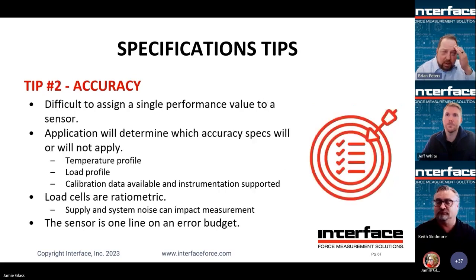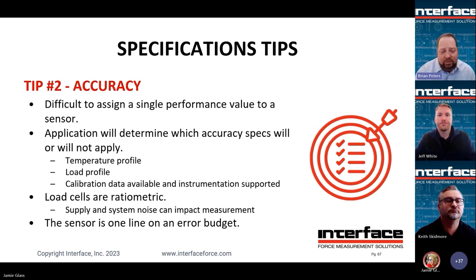All right, next one. So accuracy. We had a lot of specifications that are under that accuracy header. It's really difficult to just assign a certain number, but really it comes down to understanding which specifications will apply in your particular application, right? Which ones can you remove, which ones factor in, which don't. It's going to come down to the temperature profile of the test. If it's constant temperature, good. You can move all the temperature stuff off the table. It also comes down to your load profile. Like you heard earlier, if you're only doing a single ascending test, hysteresis, for example, doesn't matter.